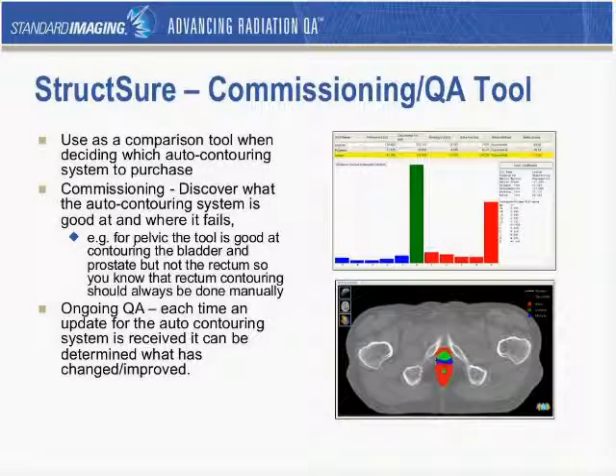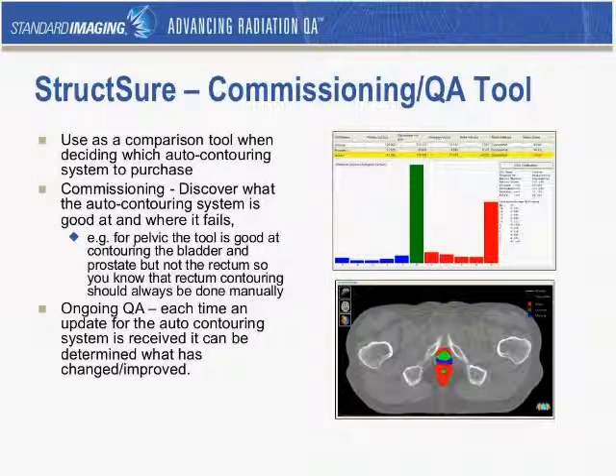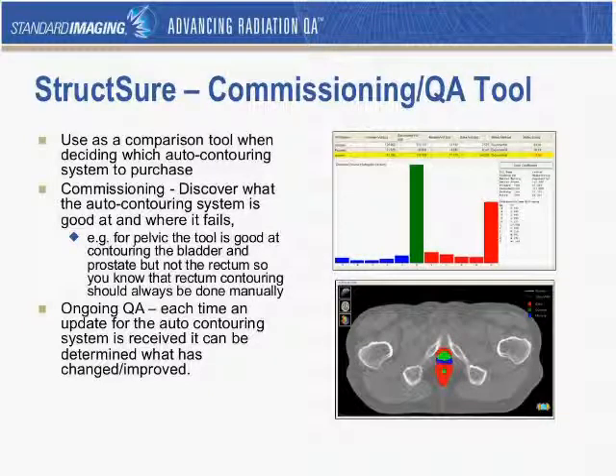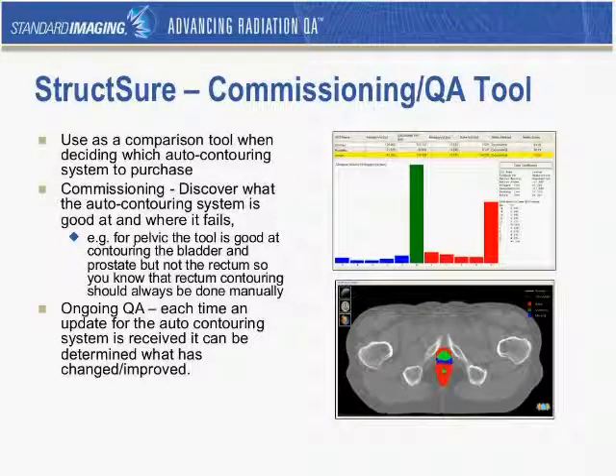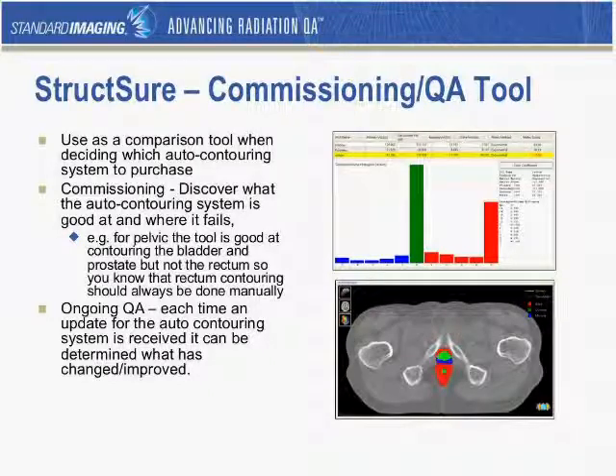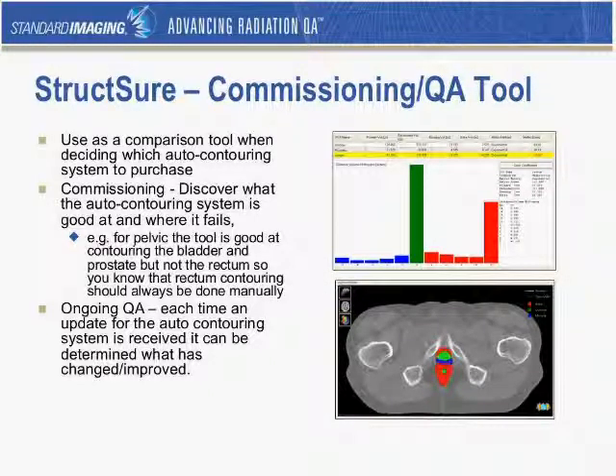StructSure was originally designed as a commissioning and QA tool for auto contouring systems. The idea was to use it as a tool when deciding on an auto contouring system to purchase — comparing each one to figure out what they're good at. Once you decide on a tool, you could use it to commission that tool, discover what it's good at and where it might fail, and then inform planners accordingly. And for ongoing QA, like any software in a radiation oncology department, when a new version comes out you'd want to know what changed, and you could use StructSure to easily do that.